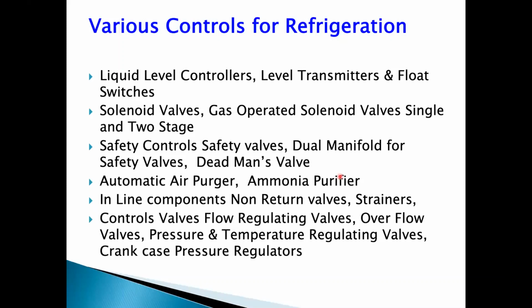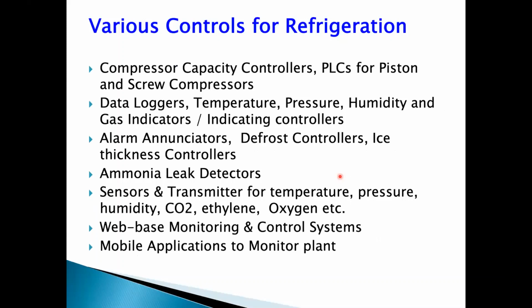When we are talking about safety, we need safety valves, like we have a safety valve even on our pressure cooker. And then we need systems which take care of maintaining pressure, like an automatic purging system, an ammonia dehydration system, and regulating control valves, pressure regulating valves. And electronically, it could be a compressor control system or a PLC system, depending on the type of compressor: piston compressor, screw compressor, multiple compressors. We need a data logging system, a data recording system. It can be a data logger for temperature, pressure, humidity, ethylene, and CO2 gases. It can have a local indication as well as centralized record and monitoring indication.